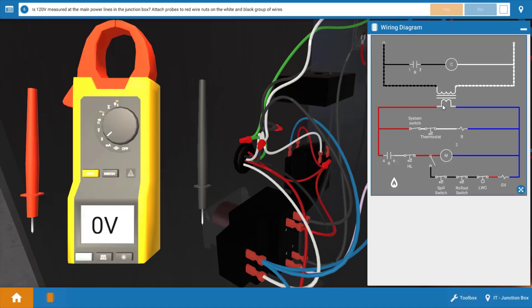One suggestion I would make, turn off the power and do a resistance check to determine which winding of the transformer is open. Oftentimes what can happen on systems that don't have any low voltage fusing is that an overload condition due to a shorted relay coil or gas valve could overload the transformer and burn the secondary winding open.